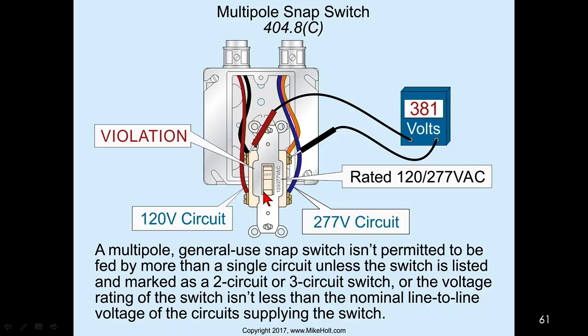So that if the lights are turned on in either bathroom, the exhaust fan runs, and when the lights are turned off, the exhaust fans are off. Maybe with some energy codes now needing occupancy sensors, this may be less of a problem, but that's a very common application. Well, still. I had a commercial building, 277 lighting, 120 volt fan. I put in a 277 rated 2-pole switch, and I was fine. But then the code says, listen, you can only do this if the switch is marked as a 2-circuit or a 3-circuit.